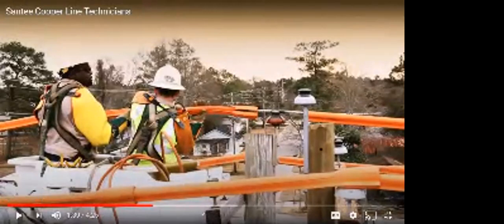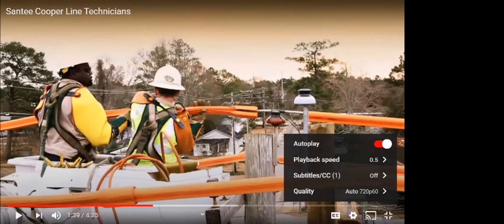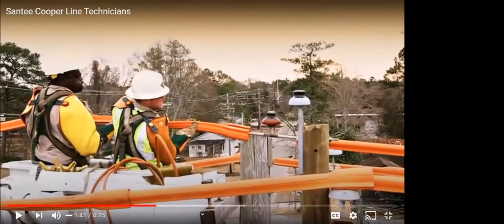Okay, watch closely here, I'm going to change this to slow motion, about half speed. This is 7,200 volts. What they're doing here is moving this conductor over to the new pole. Watch how close they get it to the top of the pole. It should not make contact with anything else. I'm guessing he's got about 2 or 3 inches of clearance there. Both of them are keeping a close eye on it. In distribution, that's okay, but that cannot be done in transmission — it's way too close.